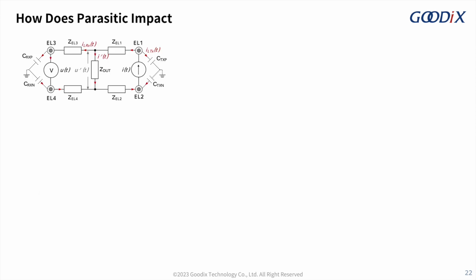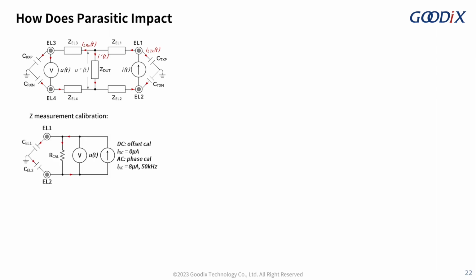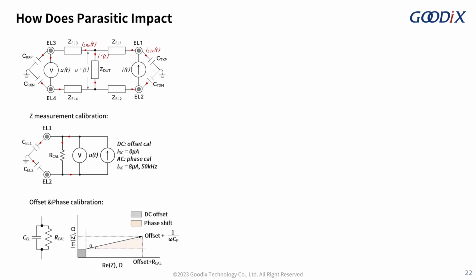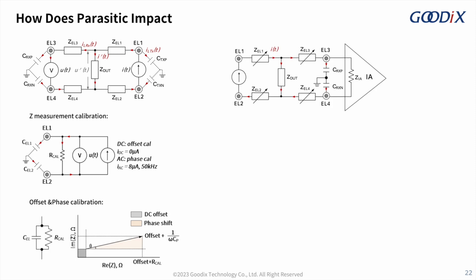The error between the excitation current and the actual current that falls on the DUT due to the parasitic capacitance of the excitation source can be solved by calibration, specifically including offset and phase calibration. Offset comes from DC bias and is a fixed amount that can be directly subtracted. Phase offset comes from capacitance. Next, let's take a look at the effect of parasitic capacitance on the receiving end.